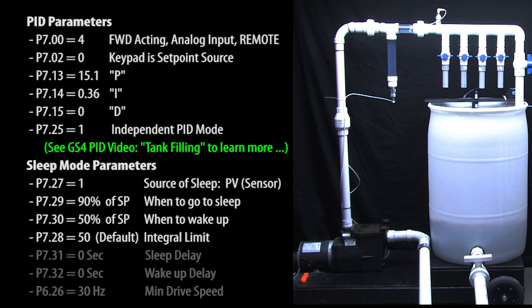Which means the integral term will continue to grow the entire time the drive output is sleeping. So when sleep mode wakes the motor up to start pumping again, it's going to take a long time for PID to settle out because it has to wait for that integral term to settle out. This parameter lets you put a cap on how big that integral term can get. Now how bad that gets depends on your system configuration. The default value we have here works fine for this system so we'll just leave it there. I just wanted to make sure you knew you had that option available to you if you needed to use it.